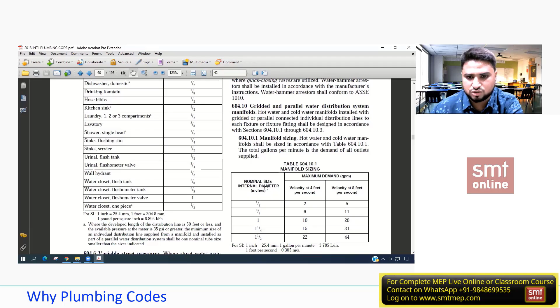Now you can see some velocities are also given. For half inch nominal pipe size, the velocity should not exceed 4 feet, and for others it's 5 to 8 feet. Don't worry, we'll be coming back to this later on.